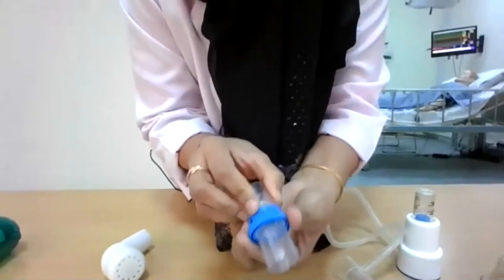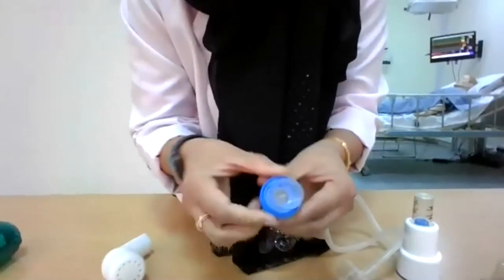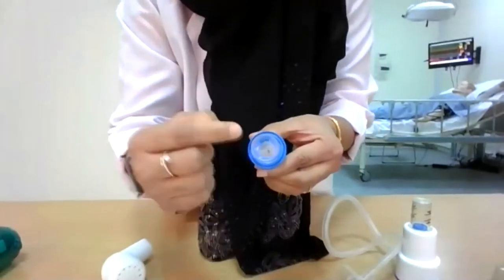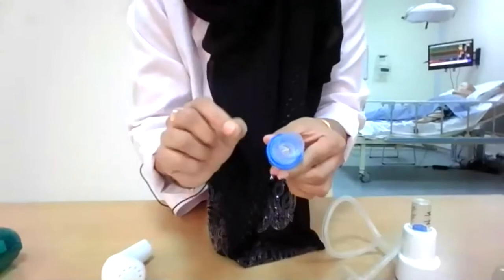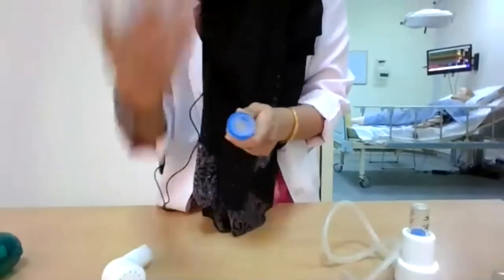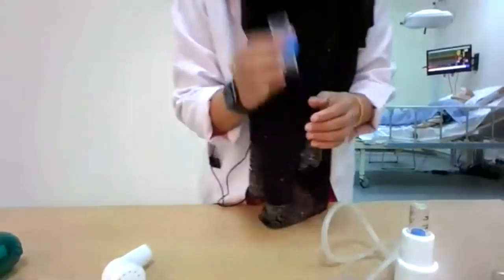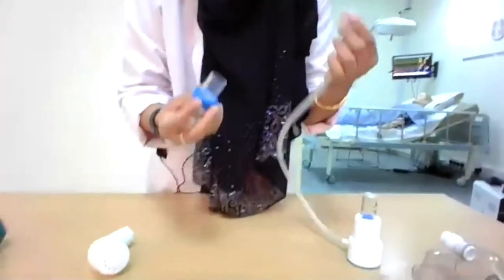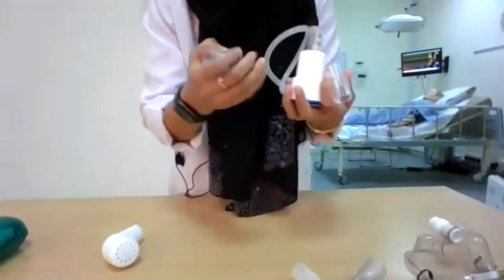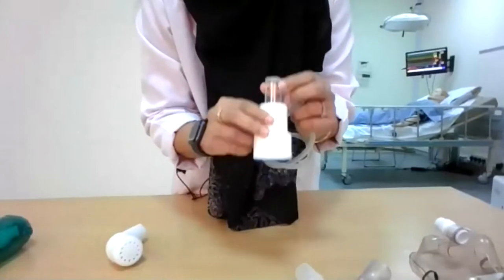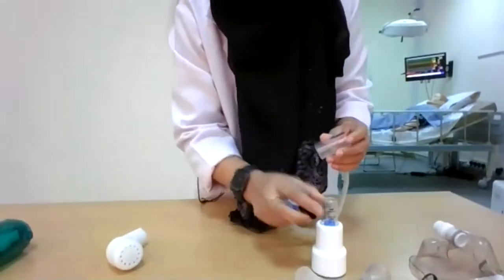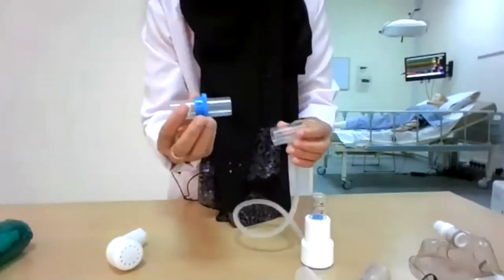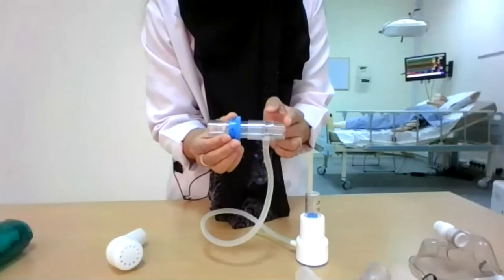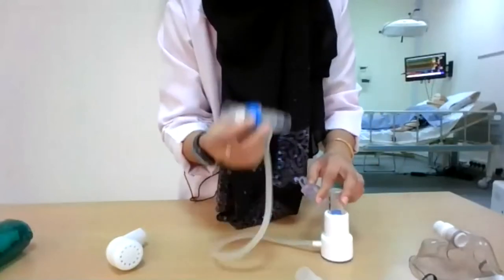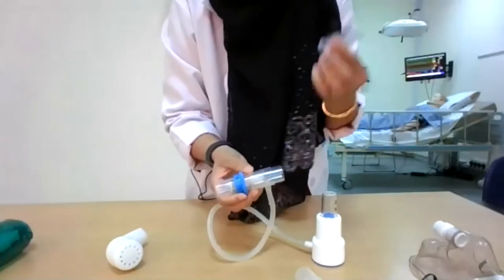When I place it on resistance 1, the patient will have the minimal orifice. The patient has to exhale through the minimal orifice so that it will generate very high pressure. It will create high resistance, and the patient has to exhale through it. Then the resistor is connected with a manometer which has a pressure level. The patient can visually monitor how much pressure is being generated. So this is the pressure indicator. I will connect the resistor along with the pressure manometer, and the other part of the device is an interface. This interface can be a mouthpiece or a face mask as well.